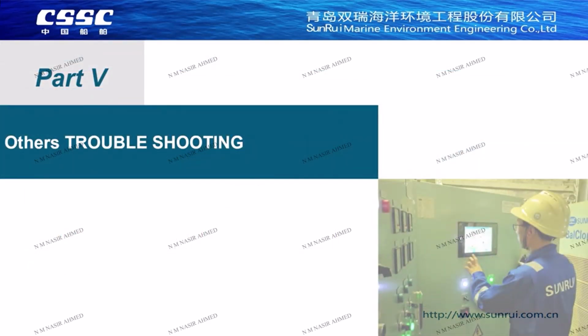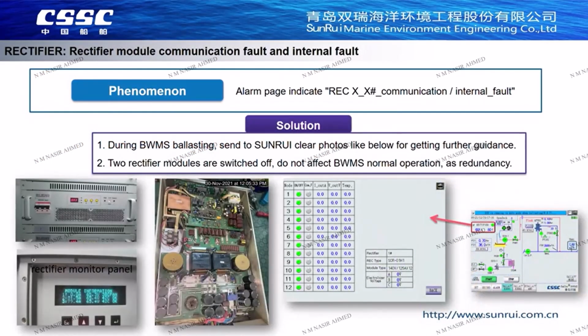Part 5. Other troubleshooting. Internal fault and the communication alarm of the rectifier. Because the rectifier is professional equipment which is not suitable for ship staff to inspect on board themselves, it is recommended to feed back relevant photos of the faulty module to Sunrui for further analysis when the system is running. The photos include a clear front view of the faulty module indicating the error LED, the module fault information displayed on the rectifier local screen, and the system alarm information shown on the system HMI.